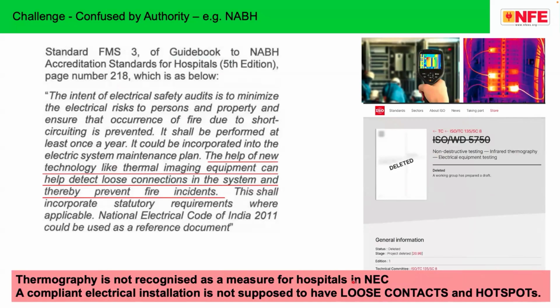There is a series of verification which is required. A compliant electrical installation is not supposed to have loose contacts and hotspots, that is the correct way. Your entire electrical installation is not supposed to have a loose contact. You forget about loose contact. Now what we do is make an unreliable installation with a lot of loose contacts, then try to find out where the loose contact is. This is not the correct way.